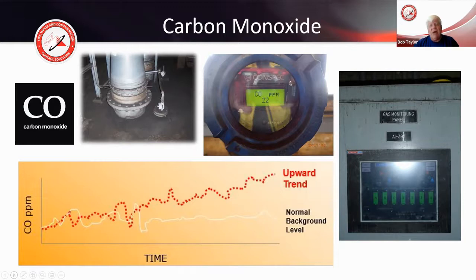It's not about the instantaneous level that all of a sudden it gets to X parts per million and everybody jumps and reacts. It's really about understanding the increases. Often it will take time before it gets to that explosive range. And if you're monitoring the trends, you can detect something's developing sooner, act on it before the conditions worsen. So there is the methodology out there to detect.